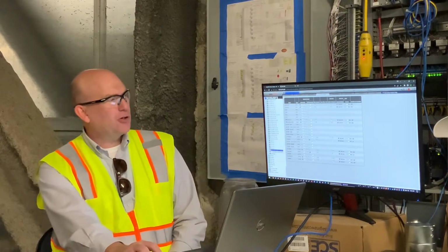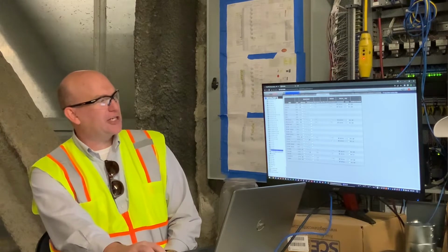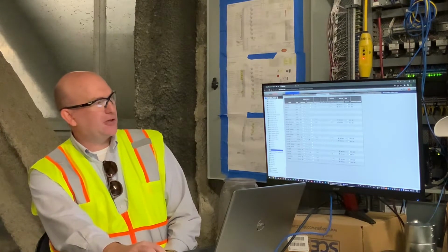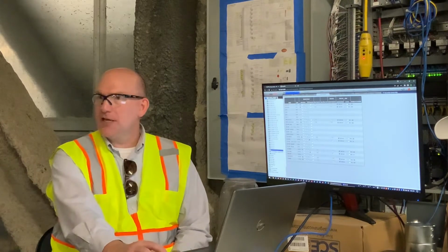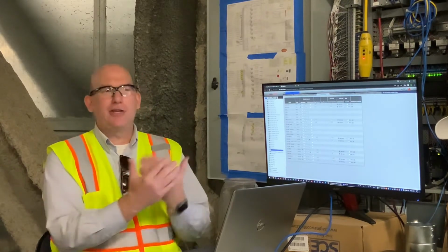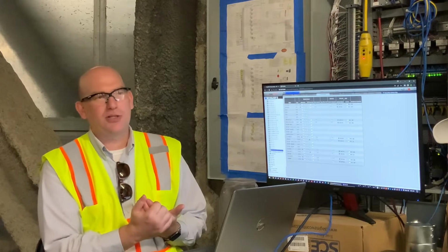So maybe when you're troubleshooting, you want to come here and you want to change that time frame for that particular point, and you can do so right here. You can change the 5 minutes down to 30 seconds. And now you've got a sample every 30 seconds, and you can see what's happening with the system.